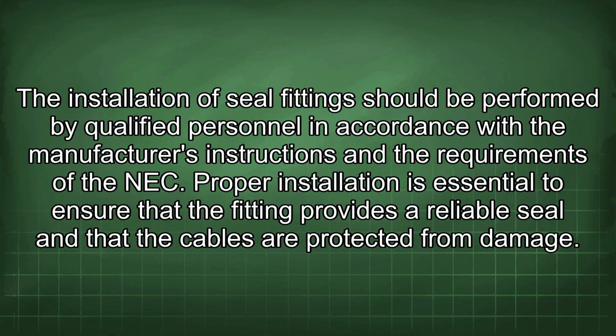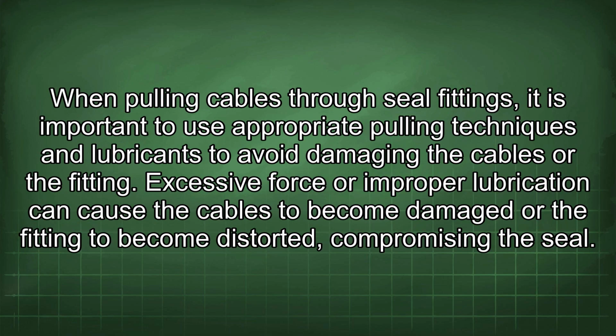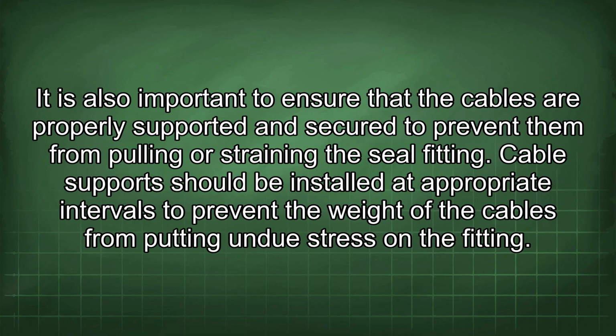When pulling cables through seal fittings, it is important to use appropriate pulling techniques and lubricants to avoid damaging the cables or the fitting. Excessive force or improper lubrication can cause the cables to become damaged or the fitting to become distorted, compromising the seal. It is also important to ensure that the cables are properly supported and secured to prevent them from pulling or straining the seal fitting.